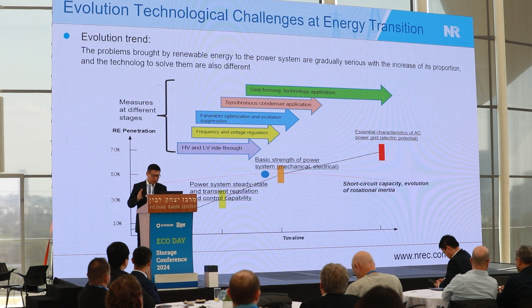So you need a more stable power system for the transition, regulation, and control - from HV and LV through frequency and voltage regulation, and also synchronous condenser application and grid forming technology should be approached in the system. If you have 100% renewable, there's a high requirement to keep the essential characteristics of the AC power system, such as short circuit capacity and rotational inertia.